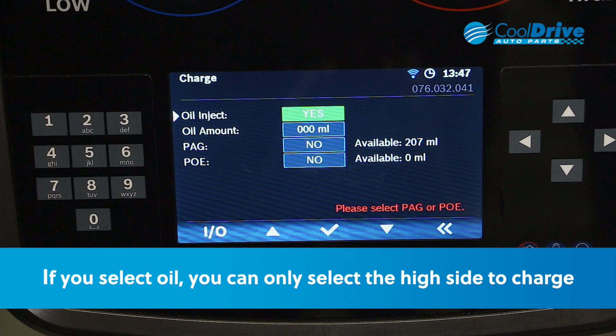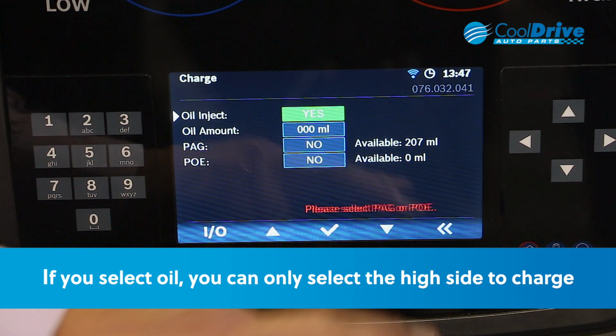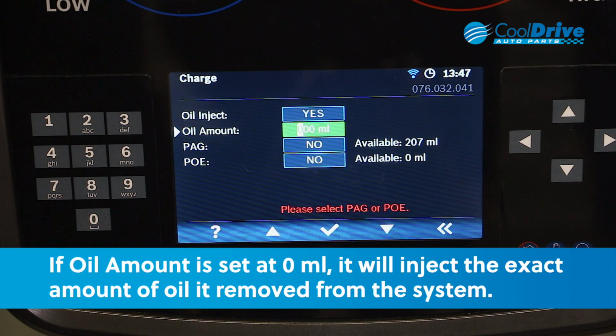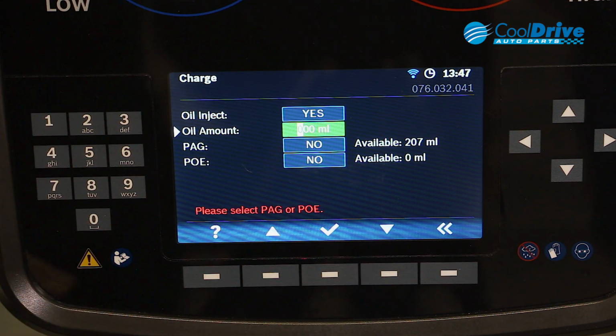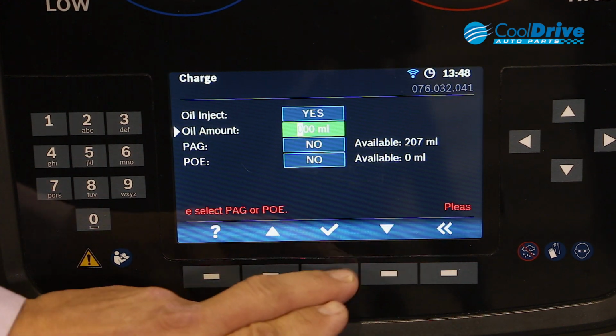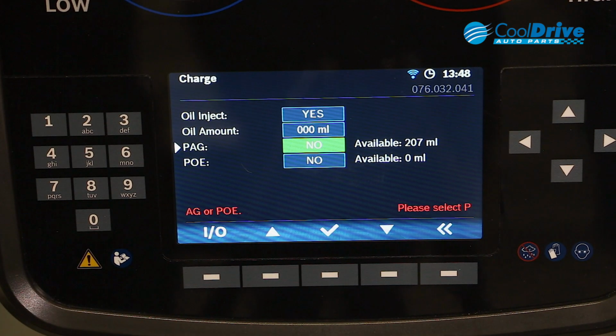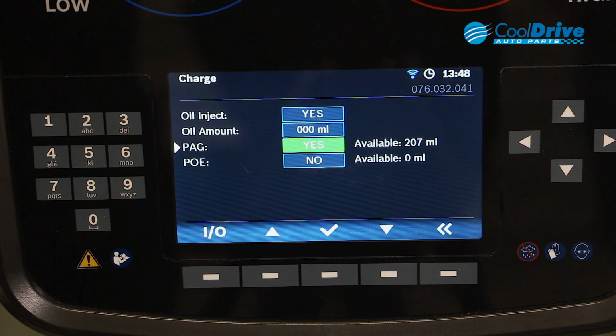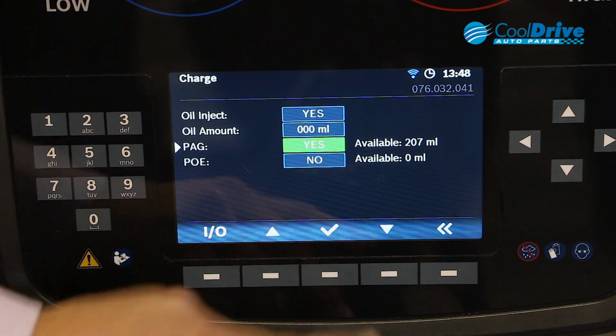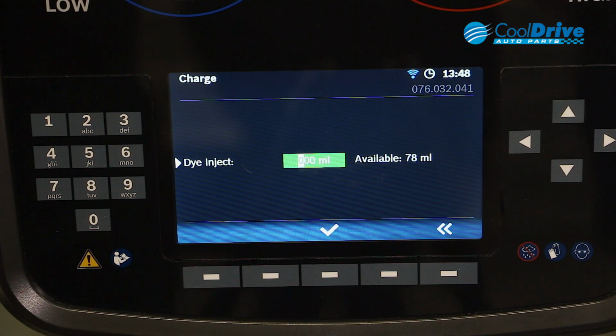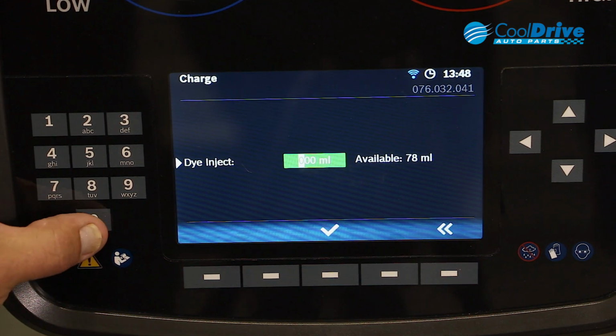So yes, we want to inject dye. If we actually leave the oil amount at 0, it will inject the exact amount of oil that it removed from the system. If you want to add oil, then we would use the numerical keys on the side. We want to actually use PAG oil, so we need to change that to PAG and leave POE off. Enter. Dye, we're going to actually inject 3 mils of dye.